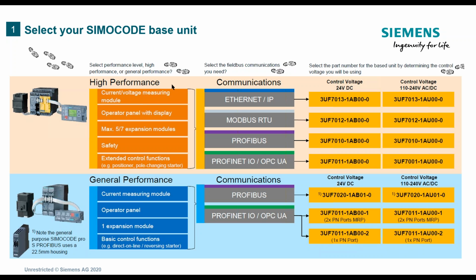And then this is the high performance, meaning that I'm able to expand 7 expansion modules, extend the control functions. I can use safety on it. Okay. And then the general purpose, I just have Profibus and Profinet. Okay, to where I'm only able to add 1 expandable card. So if you only wanted current measurement and you did 120 volt control and you were going to do just more of a simple current monitoring and motor control, I would lean towards going to the general performance side of things.